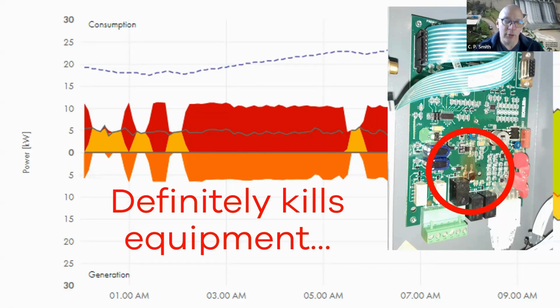With this incredibly weak grid, we've changed out 2 automatic transfer switches, which is what you're looking at here—this is the controller for the automatic transfer switch. We've also had to swap out the inverter and some other supplementary equipment.